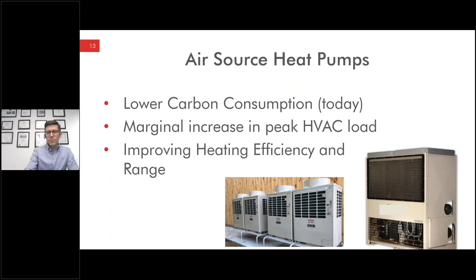And then the last bullet point here is really what we've been seeing as the improvement in the last few years, which is that the efficiency has been improving and the range at which these can operate has been improving. To talk about that very briefly, the left-hand selection you see here is one we got maybe 3 or 4 years ago from a manufacturer. The best we could get there was 104, 105 degree water at 5 degree outdoor air temperature, which we're not going to design to less than or more than in New York City. There are conditions where we would experience higher or lower than that, so we want to make sure we're able to cover the heat load, and 104 degree water as the output supply water temperature is not great.